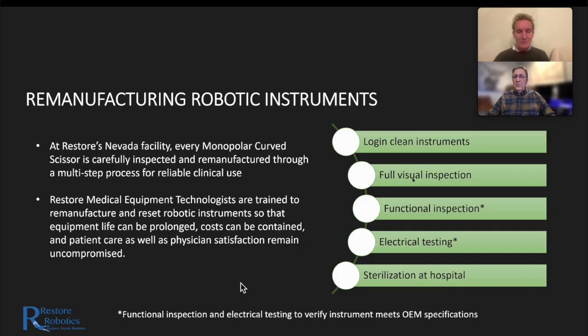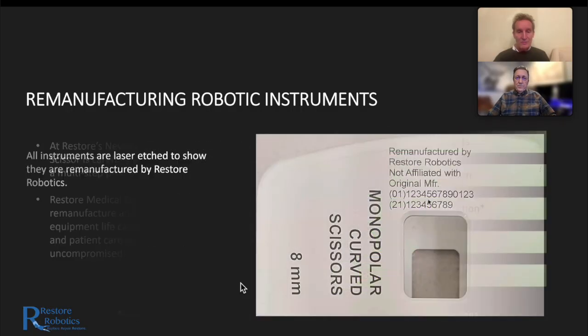They go through a full visual inspection to see if they're eligible to be remanufactured. Obviously, if they're broken or there's any substantial issues, they will not be remanufactured. If they pass that visual inspection, then they go through a functional inspection where we're doing electrical safety testing, we're checking the sharpness of the scissors, we're checking for any fraying of the cables and any other defects. And then once they complete all the testing and they pass the quality assurance, then they go into our inventory and the hospitals can purchase those instruments from us.